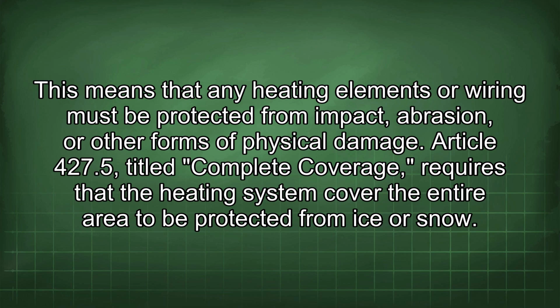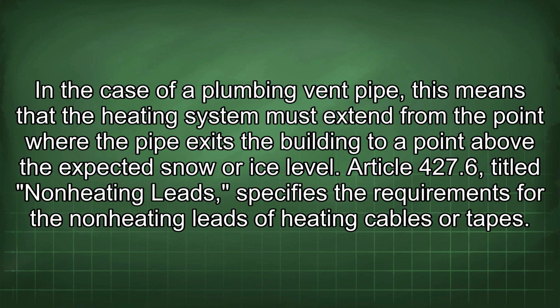Article 427.5, titled Complete Coverage, requires that the heating system cover the entire area to be protected from ice or snow. In the case of a plumbing vent pipe, this means that the heating system must extend from the point where the pipe exits the building to a point above the expected snow or ice level.